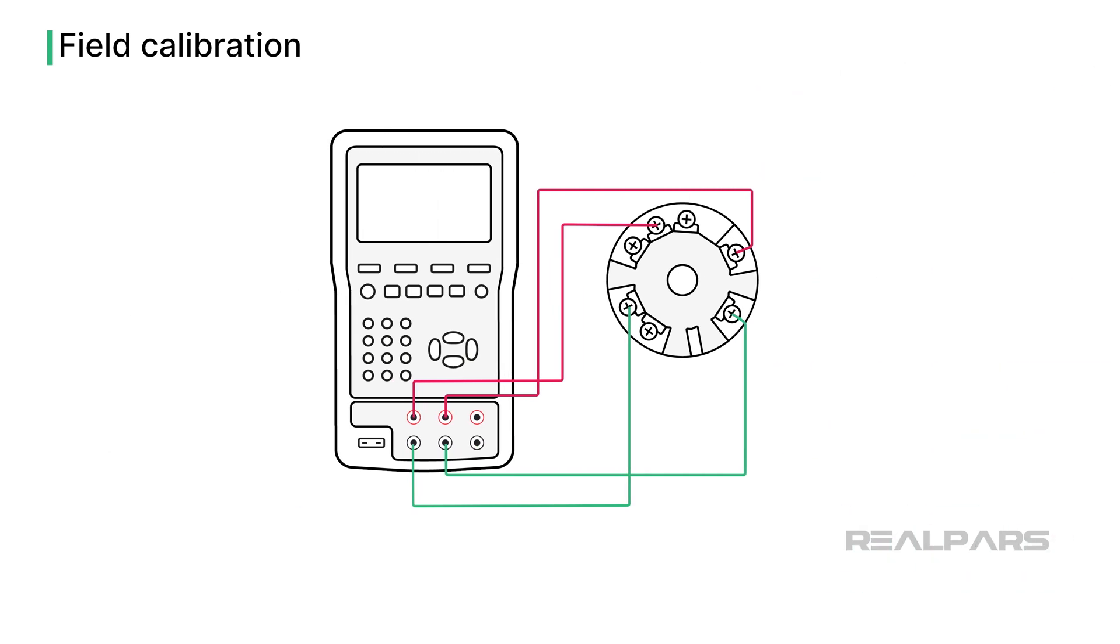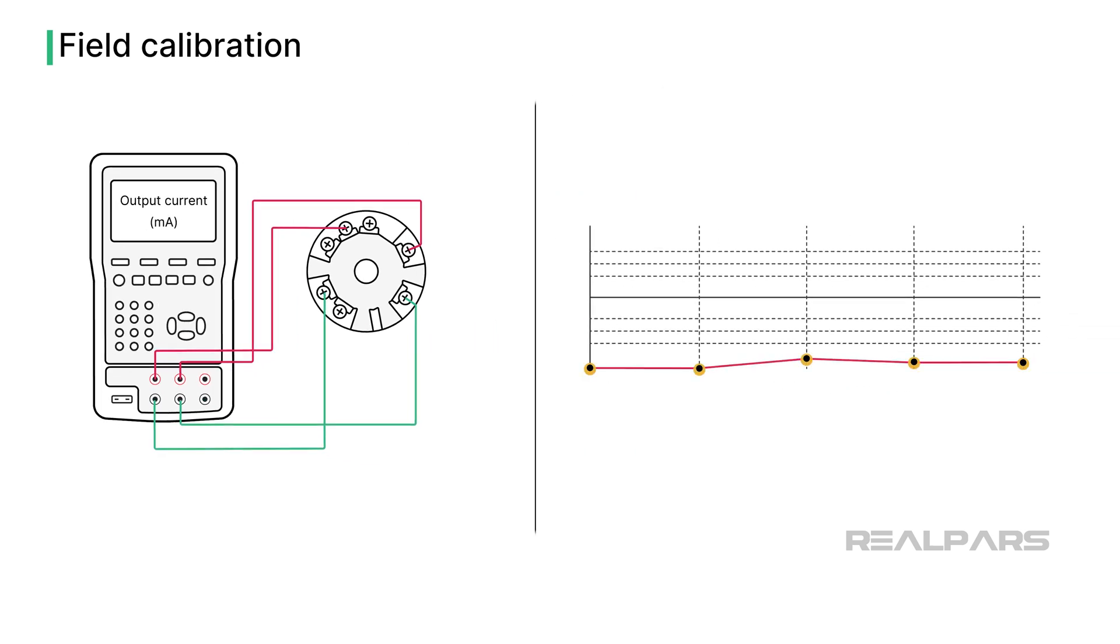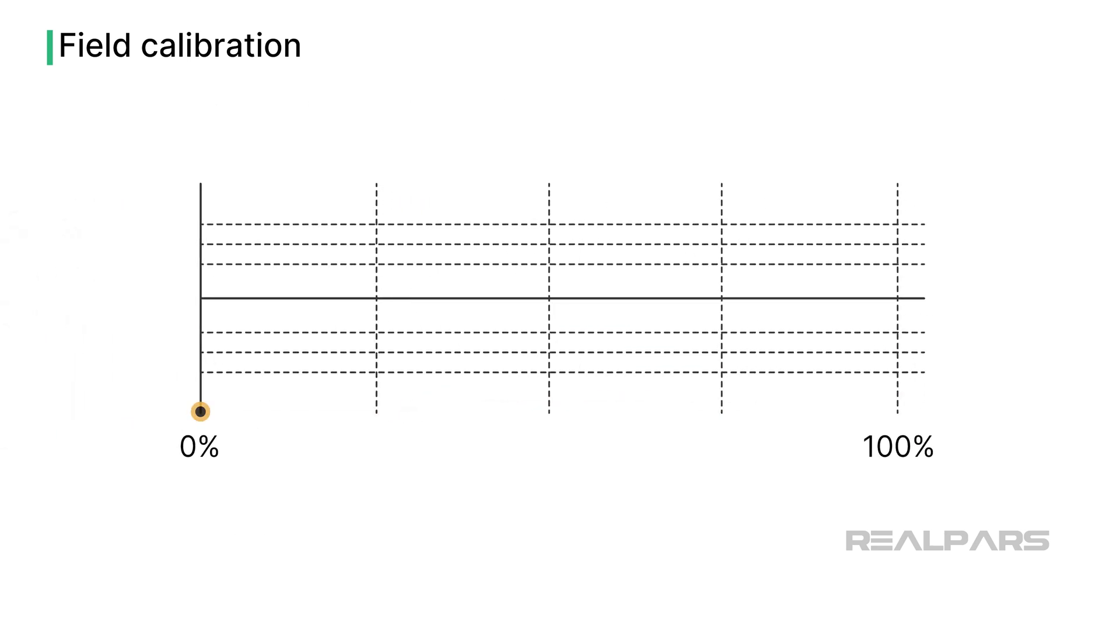The calibration process checks that the transmitter correctly interprets the simulated resistance input and produces the appropriate current output. This is typically accomplished by performing a five-point test between 0 and 100 percent of the transmitter calibration range, with tests at 0 percent, 25 percent, 50 percent, 75 percent, and 100 percent.